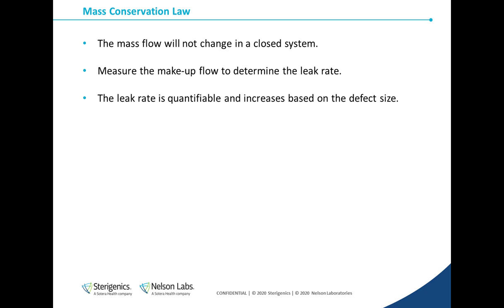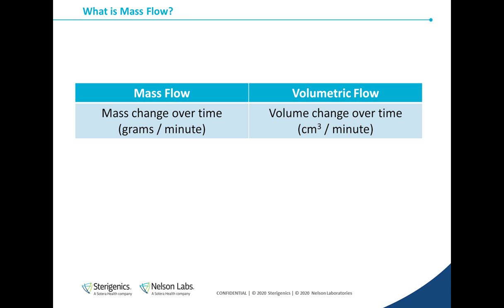The leak rate is influenced by a number of factors, like the amount of free space in the test chamber and the test method that's used, and it's going to slightly vary from one test configuration to another. So there isn't a single flow value that equates to a certain defect size. That needs to be determined with each test setup.